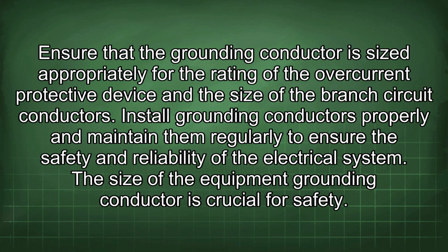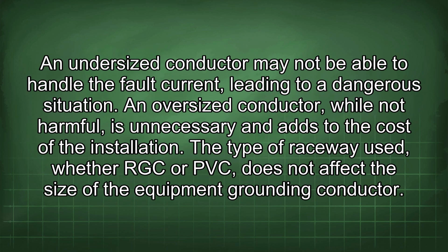Ensure that the grounding conductor is sized appropriately for the rating of the overcurrent protective device and the size of the branch circuit conductors. Install grounding conductors properly and maintain them regularly to ensure the safety and reliability of the electrical system. The size of the equipment grounding conductor is crucial for safety. An undersized conductor may not be able to handle the fault current, leading to a dangerous situation.